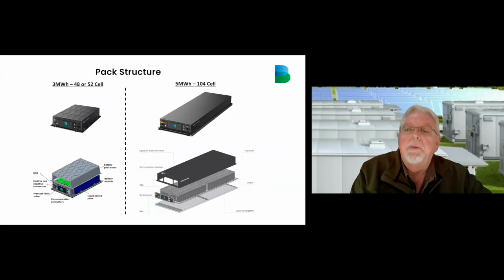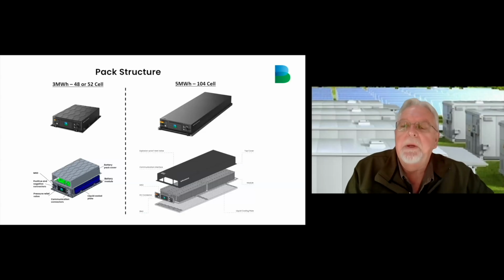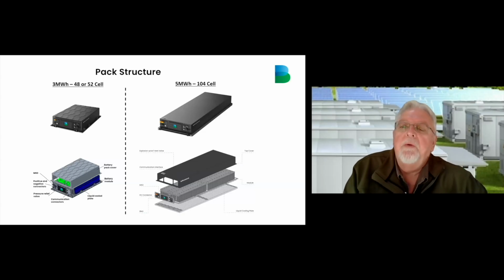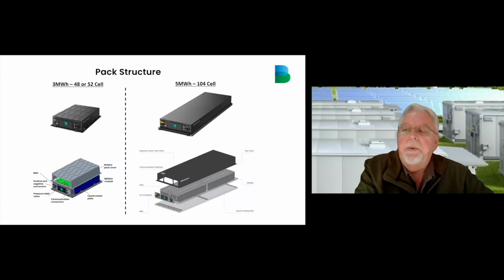Here is an example of how the liquid cooled battery pack is built. At the bottom is your liquid cooling plate, and then thermal paste is applied to the plate, and the battery cell blocks are then mounted on top of it. All temperature sensor cables are connected to the BMU on the front panel. Your front panel houses the following: the high voltage connectors, the battery management unit, pressure release valve, communication cables, and the plug-in composite probe, that is a modular sensor or monitoring unit integrated into the battery system BMS.